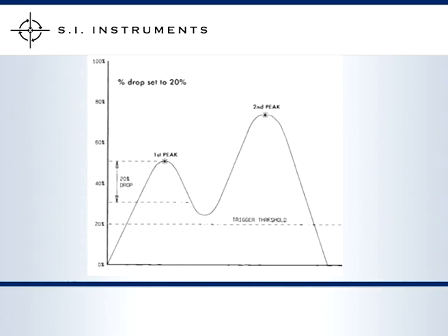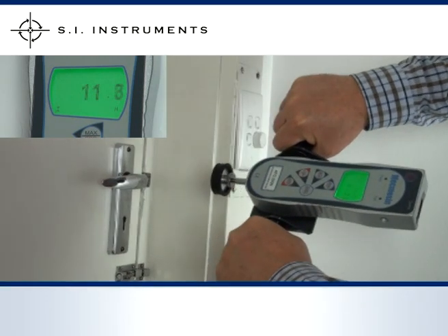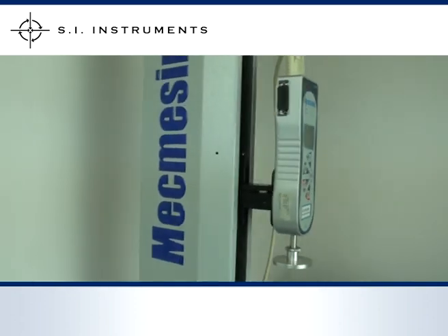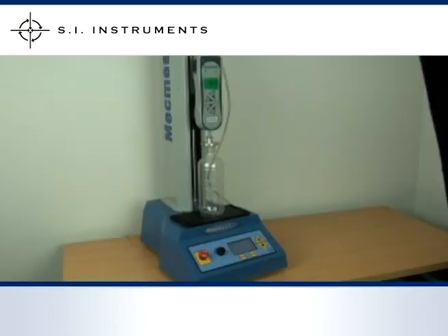Either the door is closed and you are pushing against a closed door, or the button has been activated and has bottomed out. When set, the gauge will capture the first peak of the measurement and displays this on the screen. When the Mecmesin Advanced Force Gauge is used in conjunction with the Mecmesin Multi-Test D test stand, the gauge can travel between the limit switches. It is also possible for the Advanced Force Gauge to signal the stand when the test has been completed, making this a perfect time saving operation.